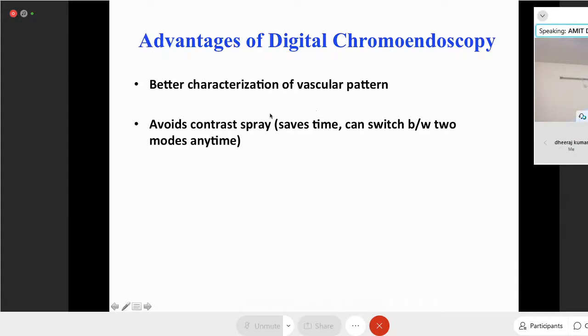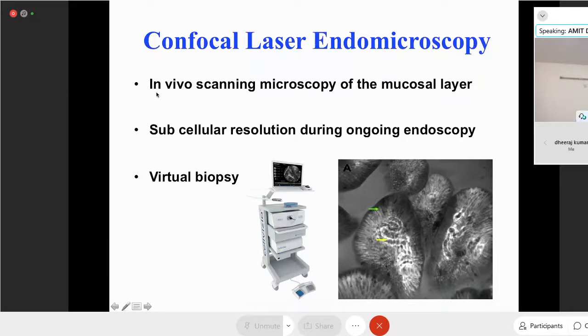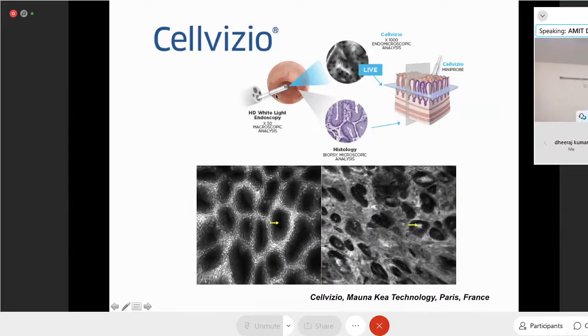Coming back to the initial slide — we have different groups of image enhancement: dye spray, digital chromoendoscopy (NBI, BLI, i-scan), and the more recent highly magnified ones like confocal laser endomicroscopy and endocytoscopy. Confocal laser endomicroscopy is basically a real-time scanning of the mucosal layer — you can actually see the epithelium and lamina propria in real time without taking a biopsy, like obtaining a virtual biopsy. The probe-based confocal laser endomicroscopy (pCLE) is a probe that passes through the endoscope channel; when it touches the mucosal surface, you get images almost like a histopathology image.